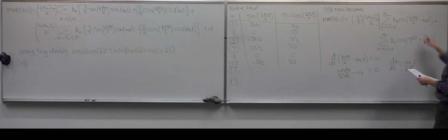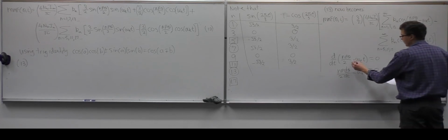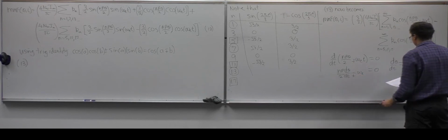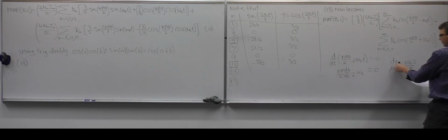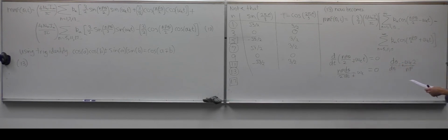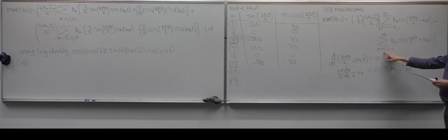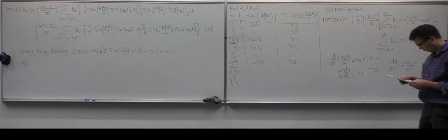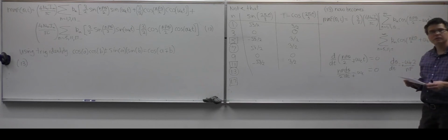And so this is a minus, this is a plus, so we could have here plus minus. So what this tells us is that these waves are traveling in the opposite direction to the fundamental. So this is of concern. If you have a large fifth harmonic, for example, you could get a lot of torque ripple. Okay, does that make sense?